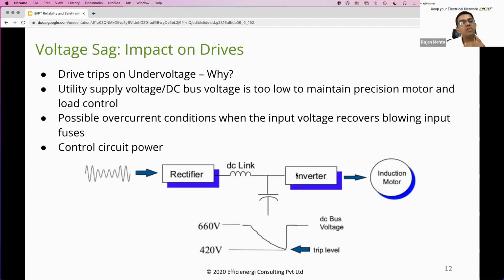And thus it is very difficult to maintain proper motor or load control at that point of time. The capacitor will try to maintain the energy for a certain time, but it may not have enough capacity. The sizing of the capacitor becomes a point of concern. So from a nominal DC bus voltage of, for example, 660 volts, it goes down to 420 volts, where the trip level of the drive comes in. This is where you see the manifestation of the voltage sag on certain types of non-linear equipment within your facility.